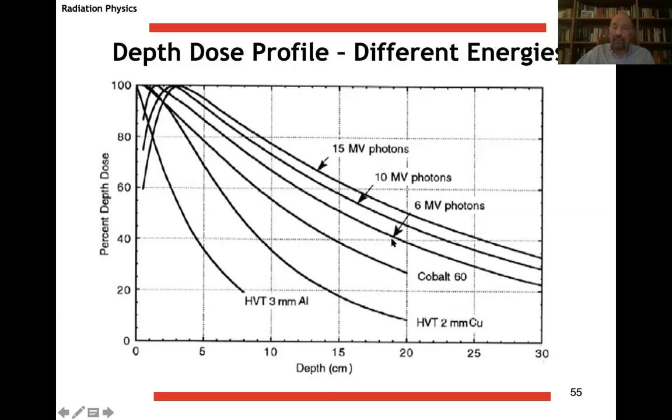And these are more typical therapeutic beams, 6 MeV, which is probably the most used these days for radiotherapy, 10 MeV and 15 MeV. They look better, they are less steep than 6 MeV, but don't forget that when you are in this region, you start to produce photoneutrons.